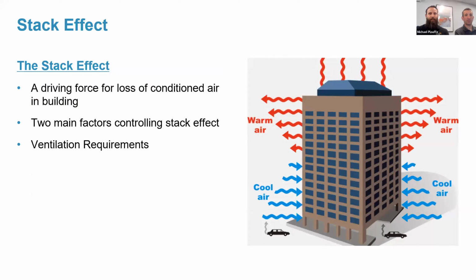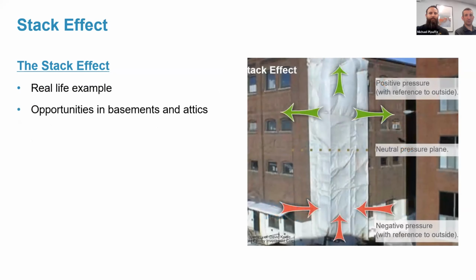We have an example of the stack effect here, where you can actually see the cool, low pressure zone at the bottom pulling that vinyl or plastic material in, and above the neutral pressure plane, you can see it inflating that material. So you can actually see where the heat is causing the pressure to expand and push that out. It's a nice visual to see how drastic it can be on even a 3 or 4 story facility, like the one we're looking at here.